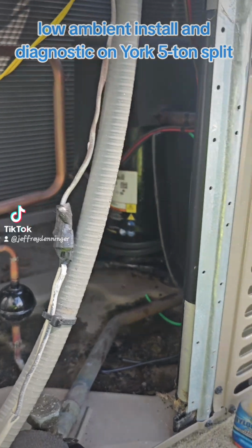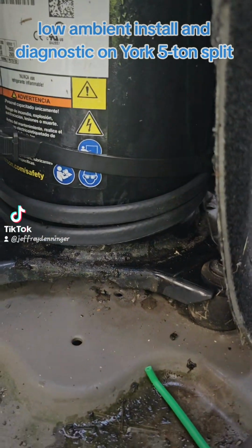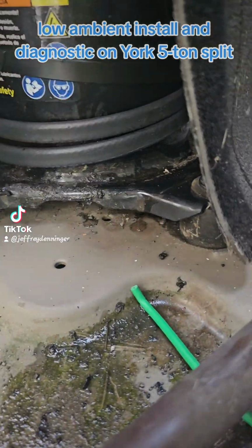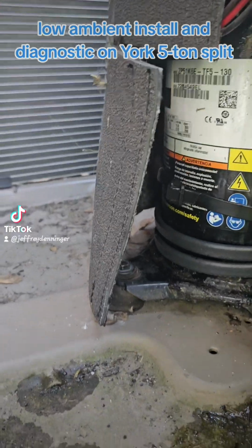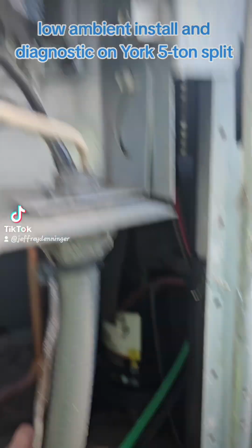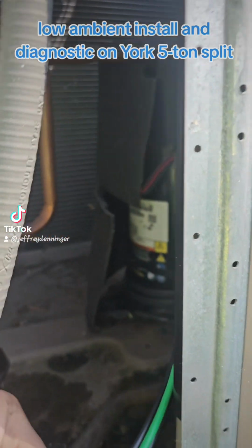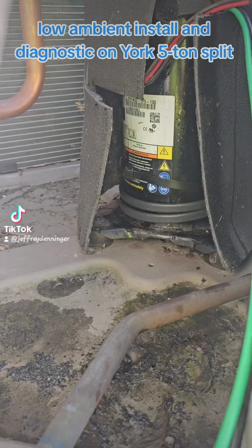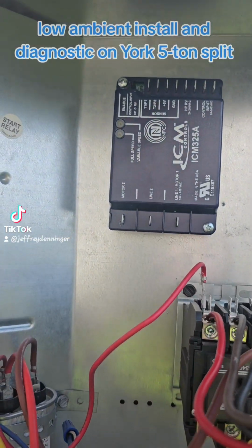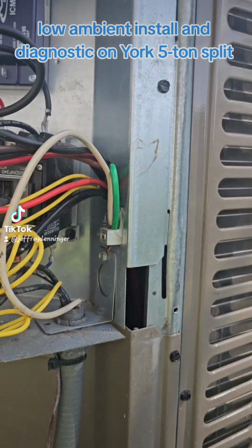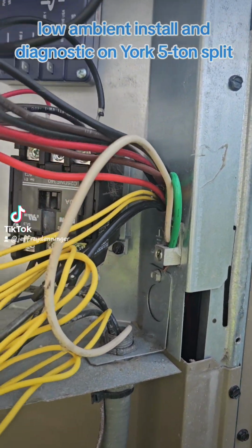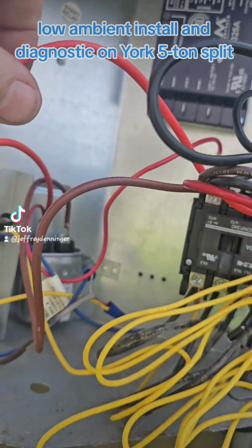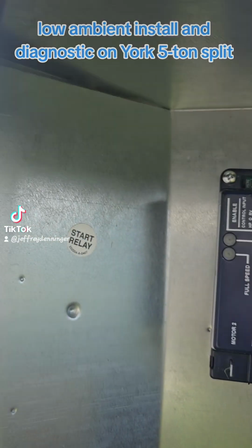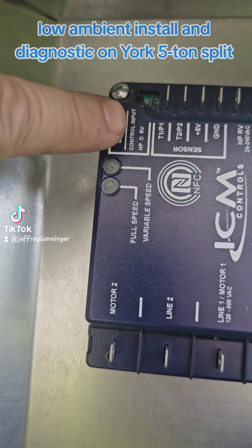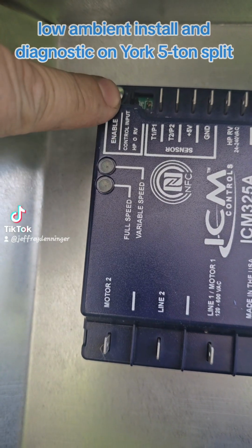Okay, I've taken off the access panel here, and we have wired in the universal crankcase heater. Relay's put in place. We still have to wire it up. That will go here onto the contactor. Okay, I got the module mounted. Pulled apart my bundle of wires here so I can find my fan motor connections so I can start wiring everything in. I also had to put a jumper on the control input here per the manual for a regular air conditioning system. This is not a heat pump.